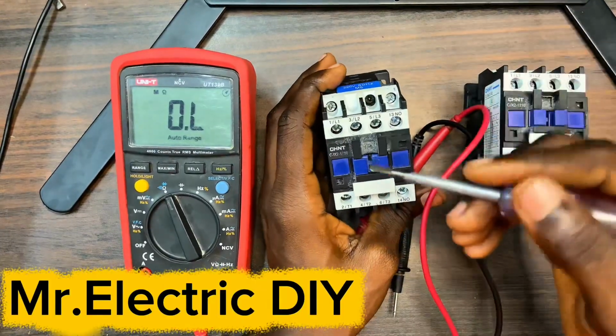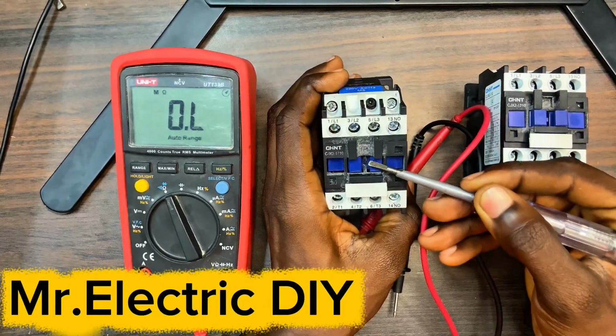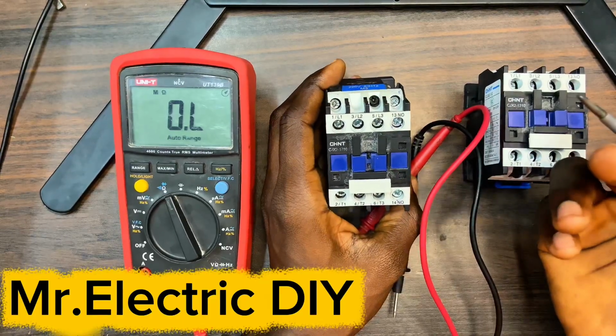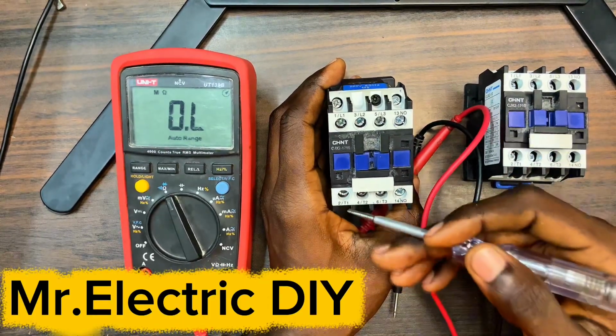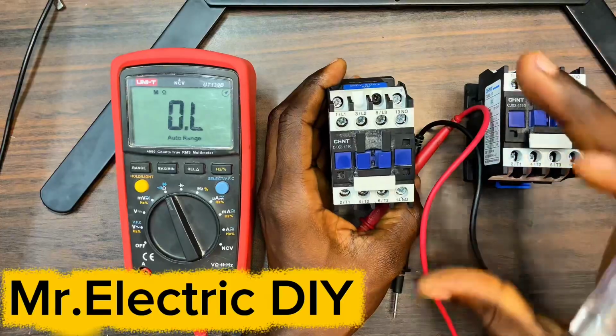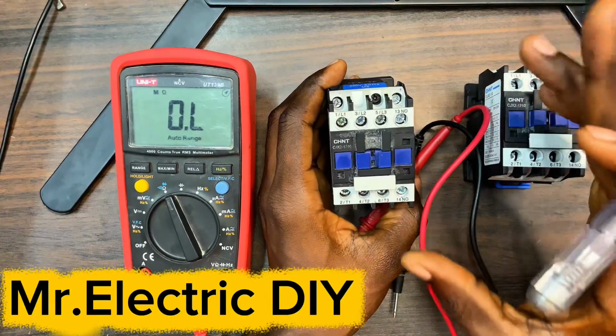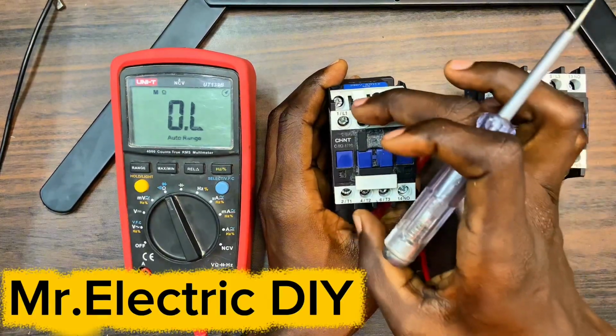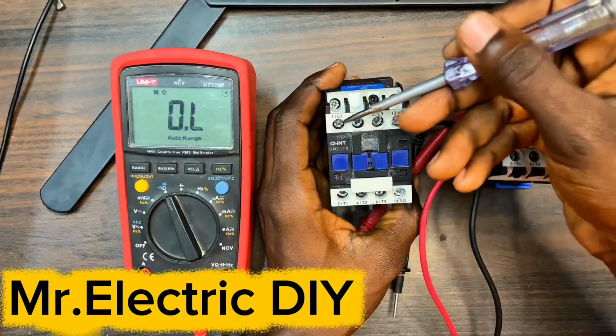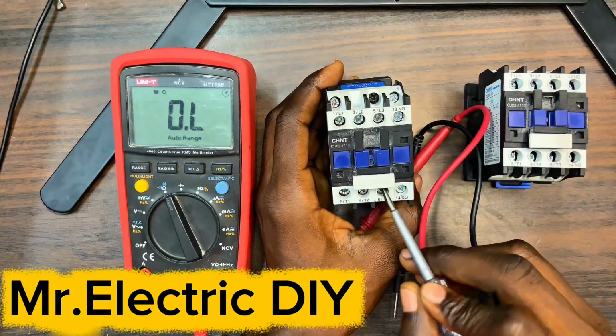Now, when you turn on the contactor, it's going to energize. But the 3-phase motor, that's supposed to receive the line 1, line 2, and line 3 current, is not receiving such current. That is when you're supposed to check the power terminals. This side is the input and down here is the output.